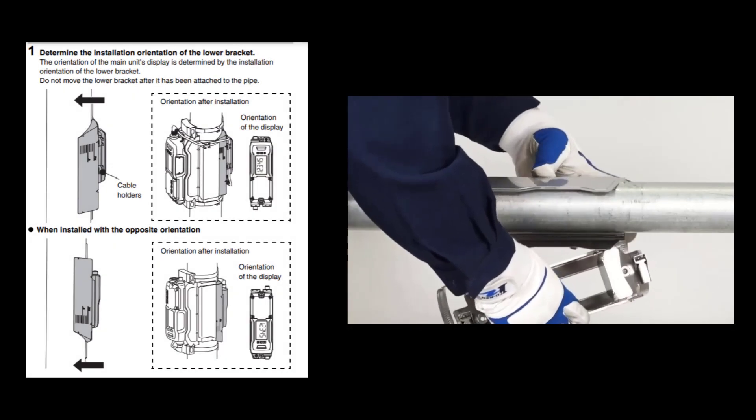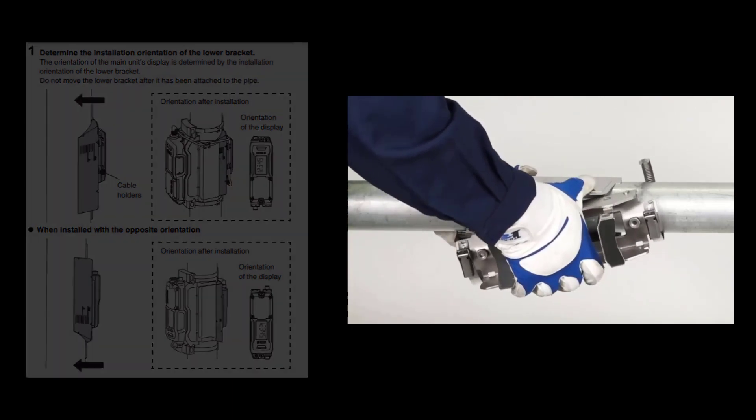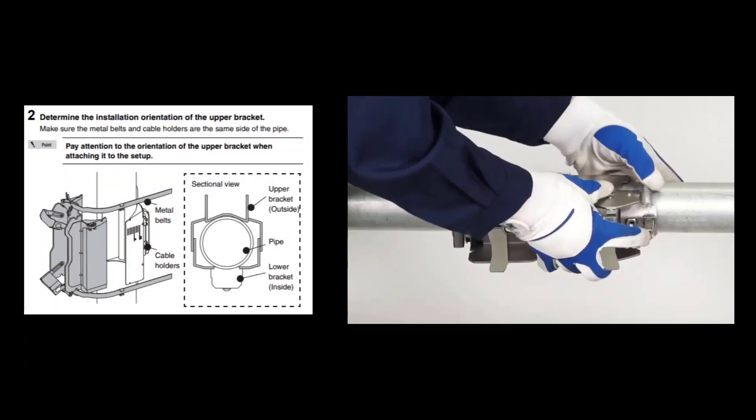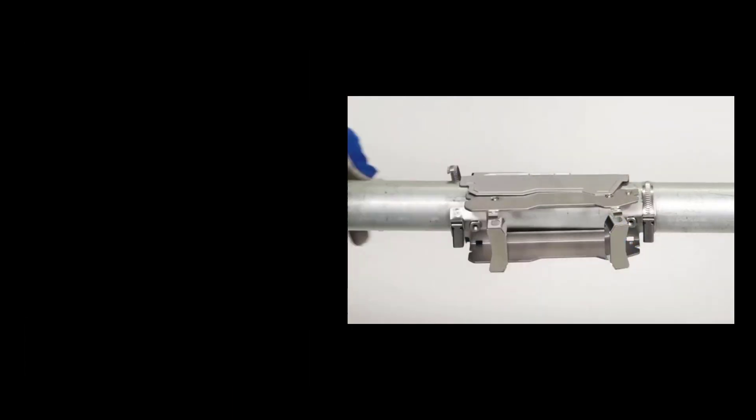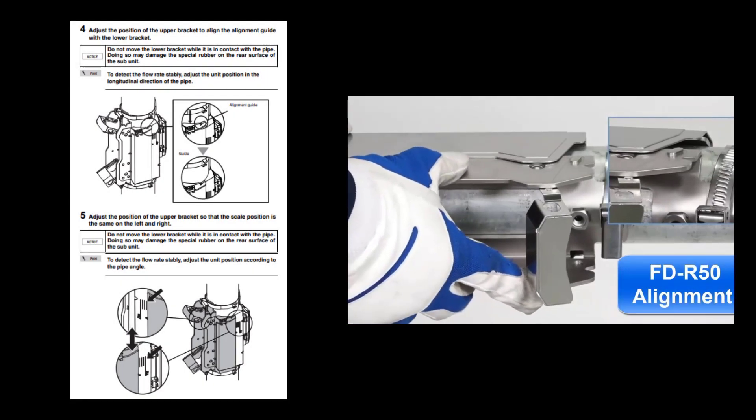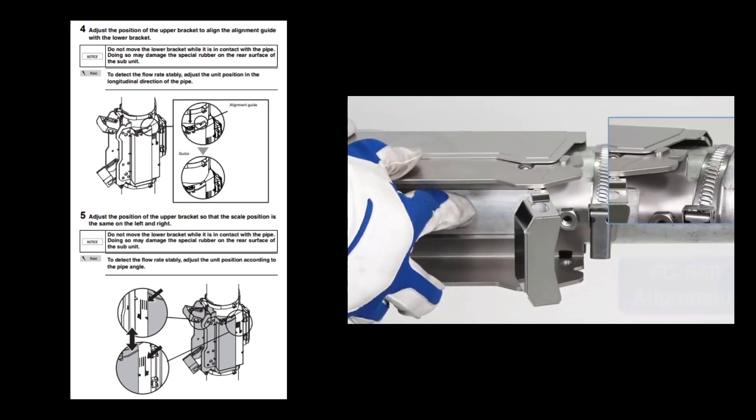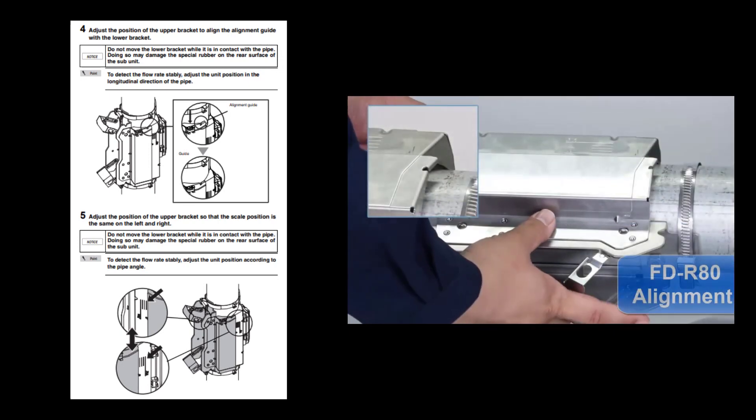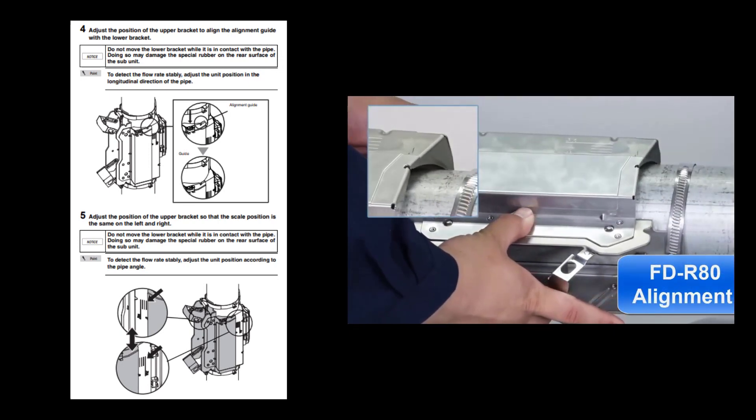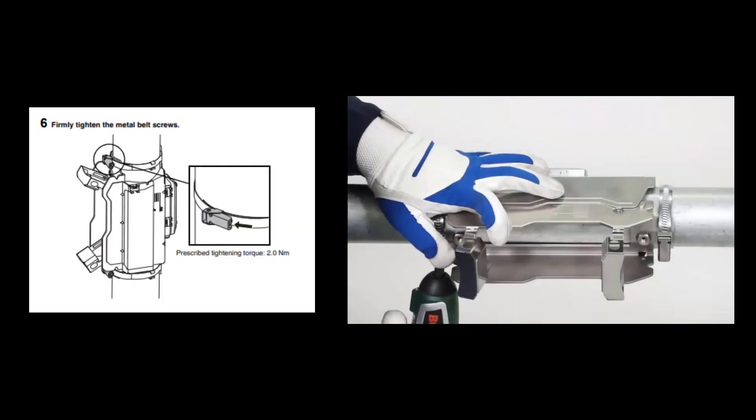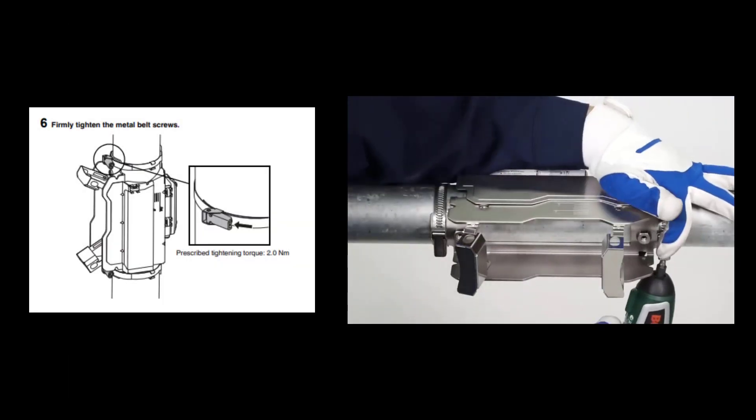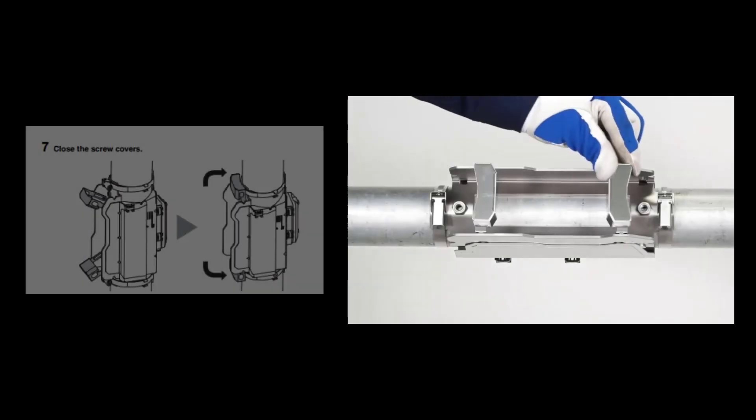Start by attaching your lower bracket. Wrap the metal mounting straps of the upper bracket around the tabs of the lower bracket and insert those metal straps into the screw brackets. Be sure that the upper and lower bracket are aligned on both sides so everything is straight on the pipe. Next, tighten both screws so that the entire bracket is evenly secured to the pipe and close the screw covers.